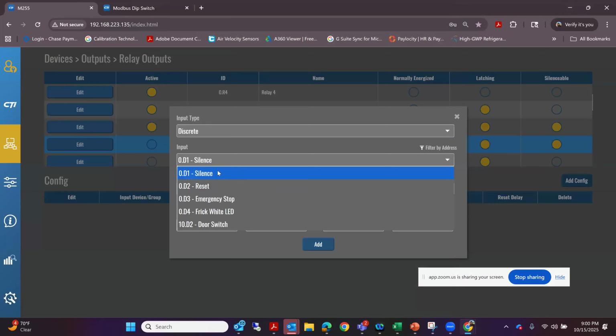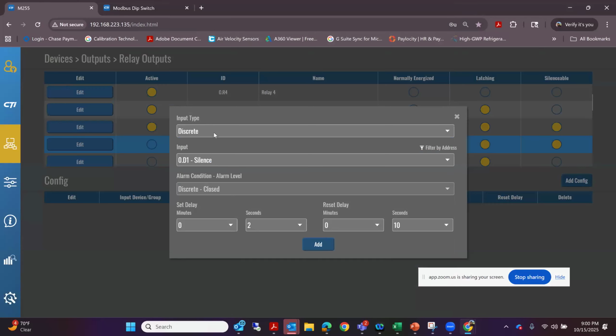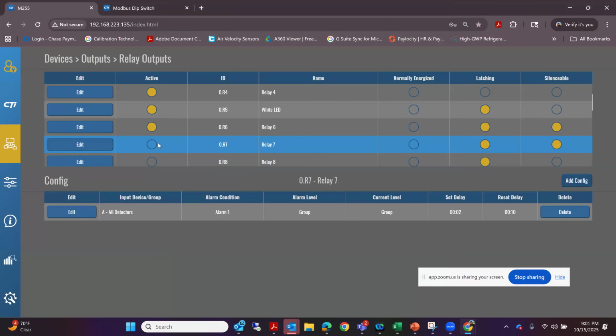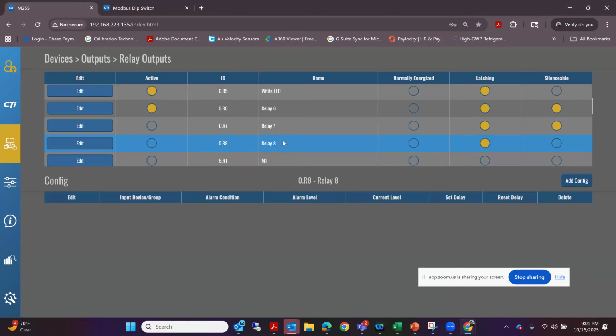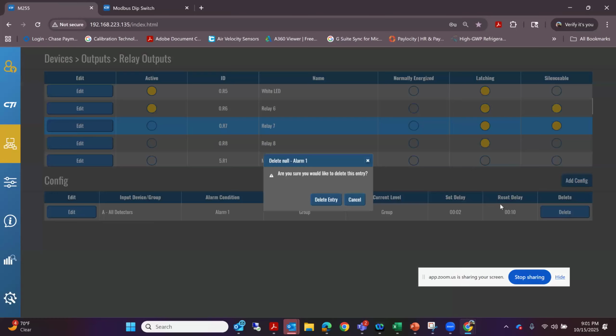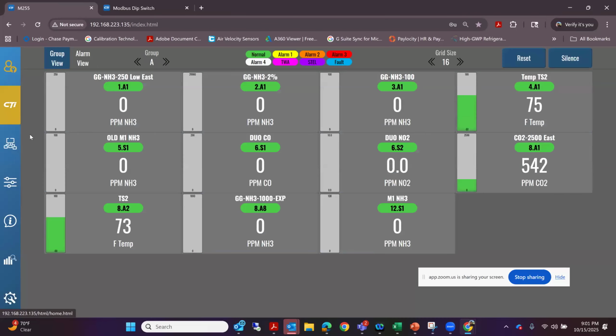So I got 4 discretes that somebody could just press a button and turn on lights if they wanted to. And so that gives you a lot of options. You could add that for any sensor alarming. I'm going to trip that horn strobe on this relay 7, and of course make it active, and then call it what it is. And so that's how easy it is to program a relay. So if you're troubleshooting through here and say, hey, I'm not seeing this relay 8 trip, you can go hit relay 8 and go look and see the configurations underneath it. And you say, well, no wonder it's not tripping. Nothing's programmed here underneath relay 8. I want to add something. So that's how easy it is to actually program these relays and to get some output functions happening there off your system.